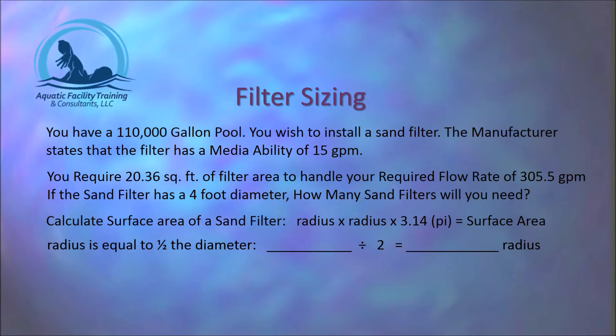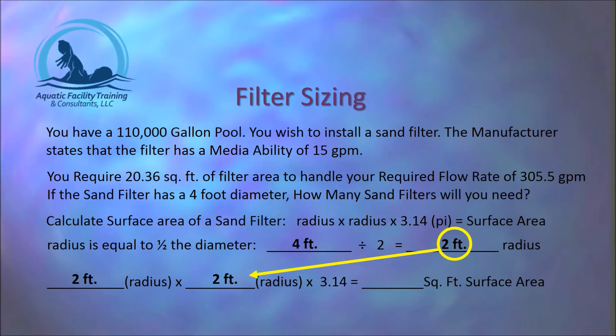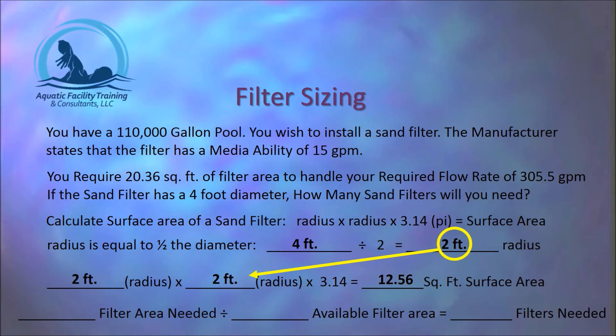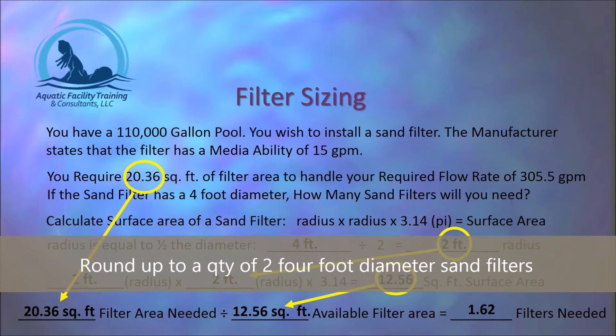Radius is equal to one-half of the diameter. Our sand filter has a 4-foot diameter, so 4 divided by 2 equals 2 — our filter has a 2-foot radius. To calculate the square foot of surface area: 2 times 2 times 3.14 gives us 12.56 square feet of surface area. To determine how many filters we require, we take the total filter area needed (20.36 sq ft) divided by 12.56 sq ft per filter, which tells us we need 1.62 filters — so we round up to 2 filters.